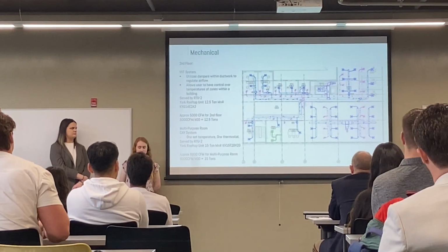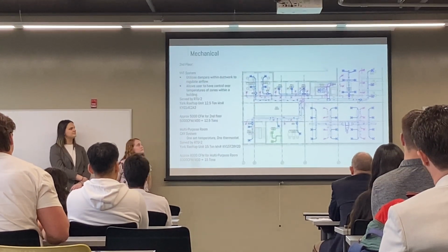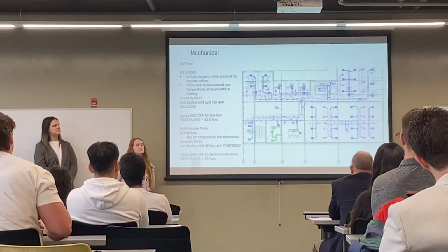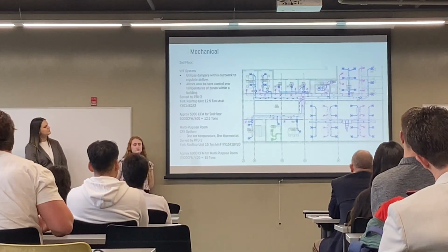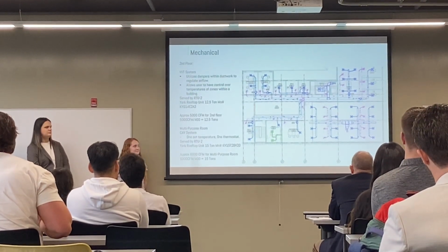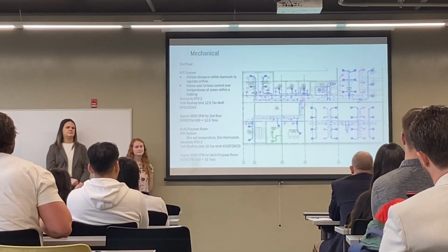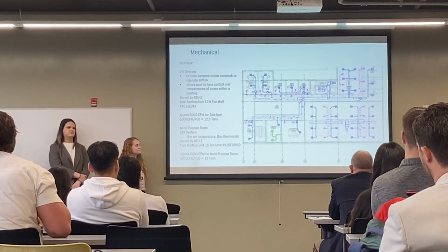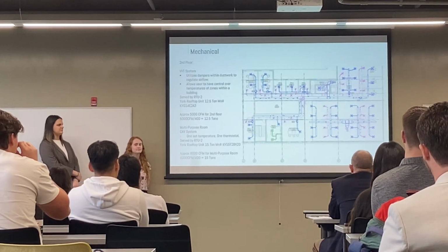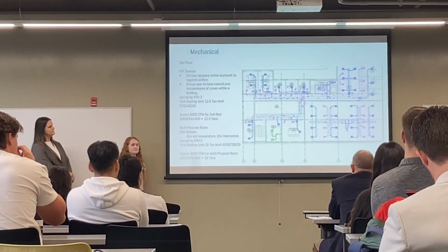So for the second floor, there's a lot of different color here, but starting off with the second floor, we decided to use a VVT system, which stands for Variable Volume and Temperature System. It essentially utilizes dampers within the ductwork to allow the user to be able to regulate airflow throughout different zones.